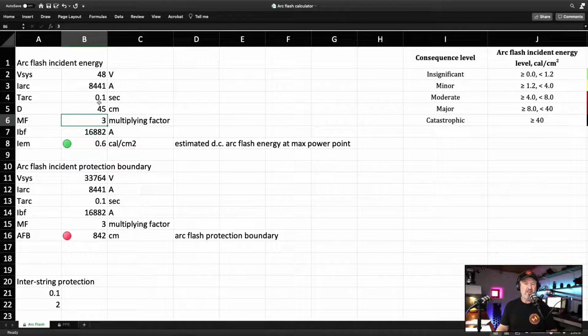The arcing time is given here as 0.1 second. You can actually calculate that from the protection device that you put in as an interstring overcurrent protection device. You can look at the current time series for it and find out what the trip time is for that product, and therefore you can put it in there. So 0.1 is given as an example in the battery standard. So it really helps to reduce that.